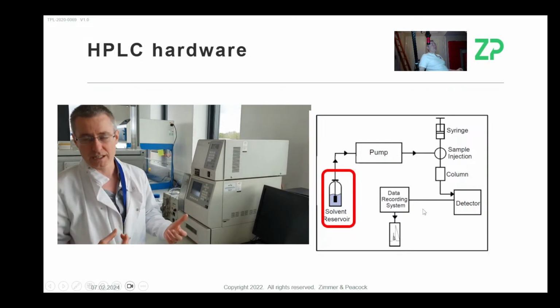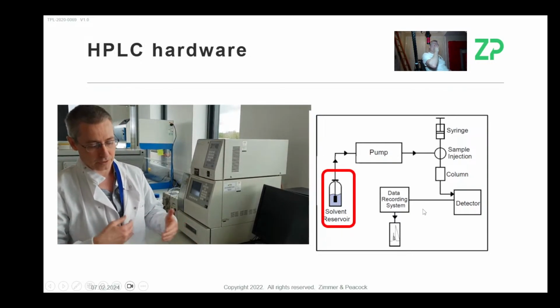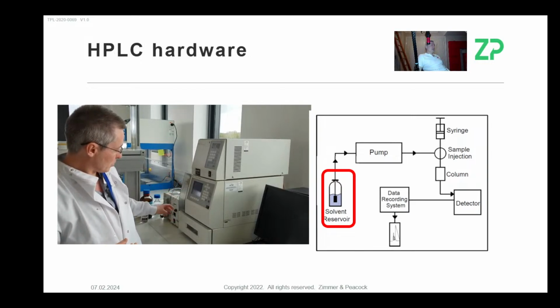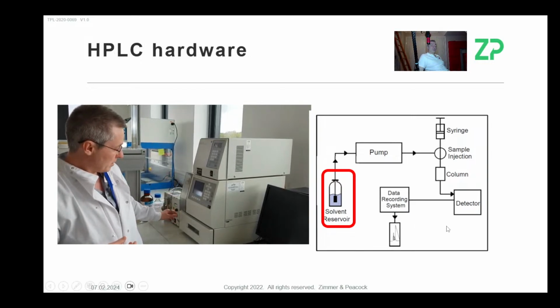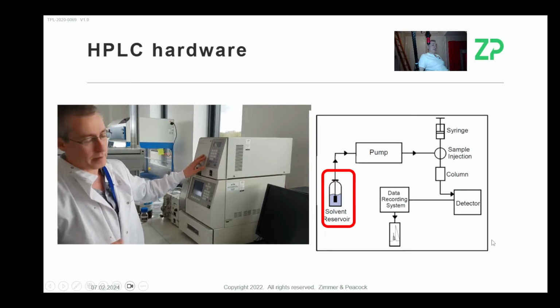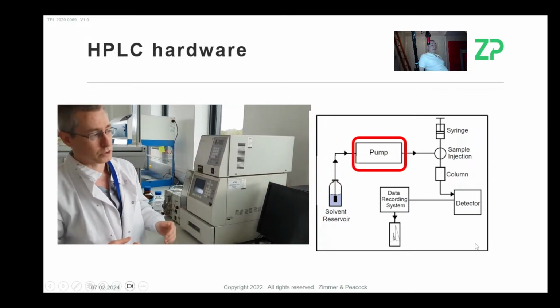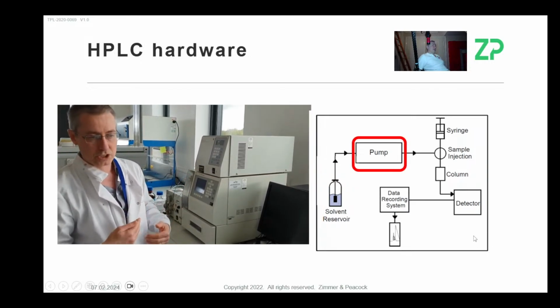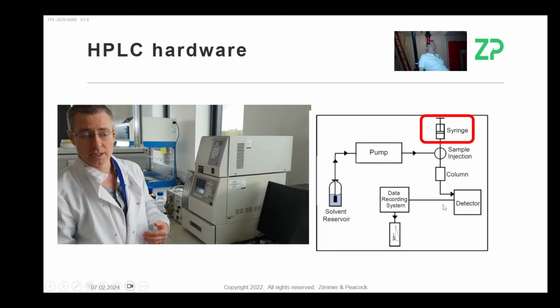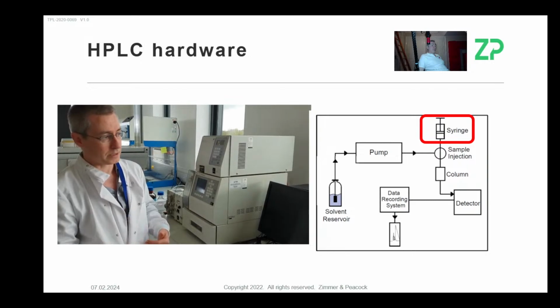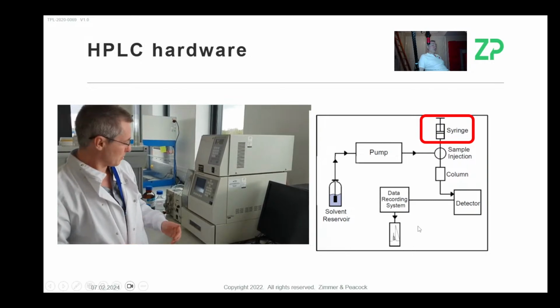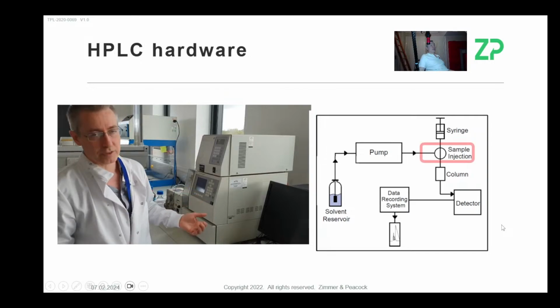It's got solvents. So the solvents, you've got to be licensed to handle these organic solvents. You can't just dispose of these organic solvents. They've got to be taken away and incinerated. The pumps are expensive. If a pump goes, you're talking about a few $1,000s to replace it. You inject the sample into it. It takes a bit of skill. There are auto samplers, but of course anything that's automated can break down.